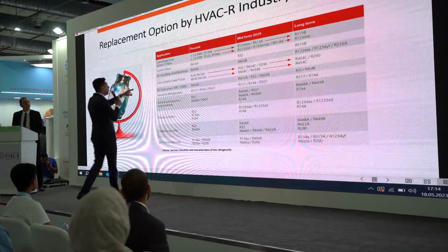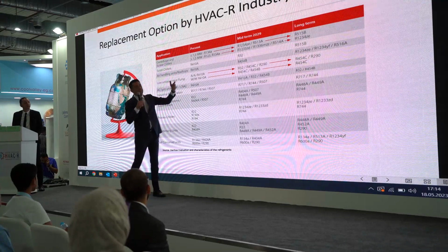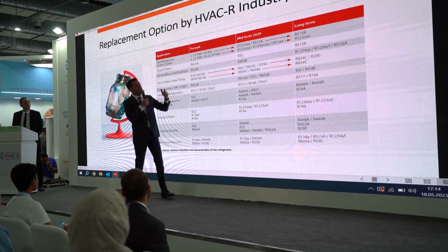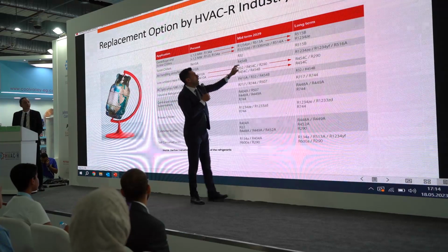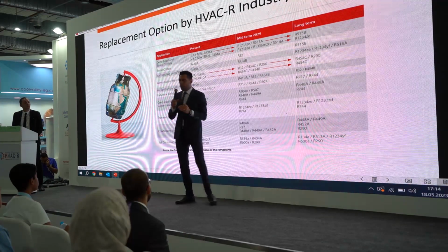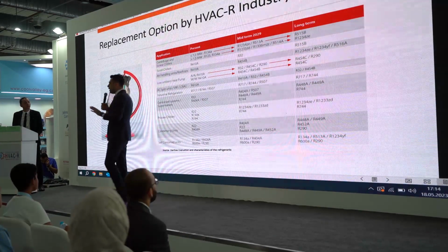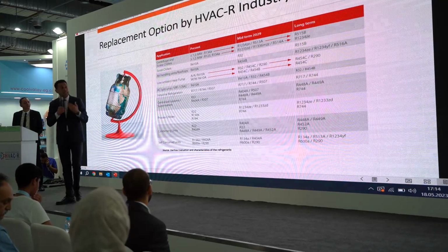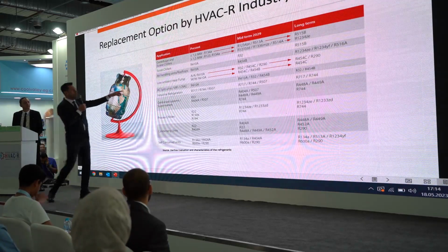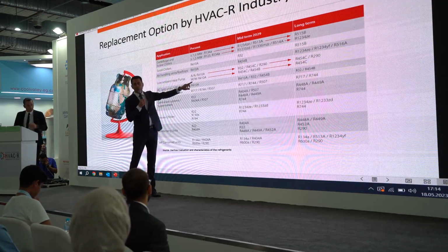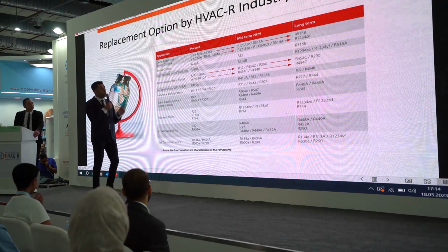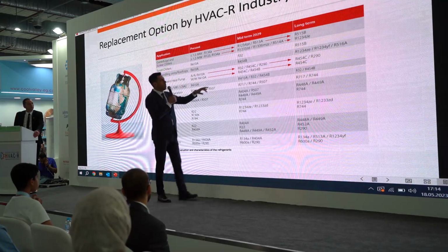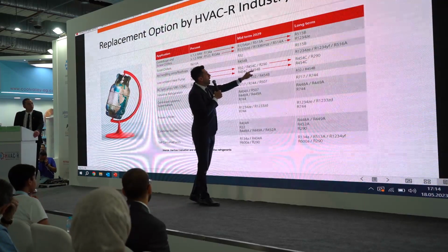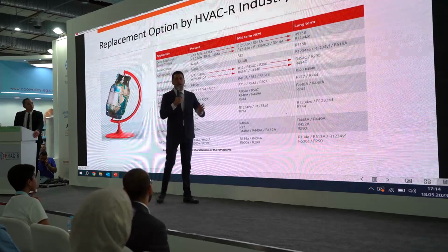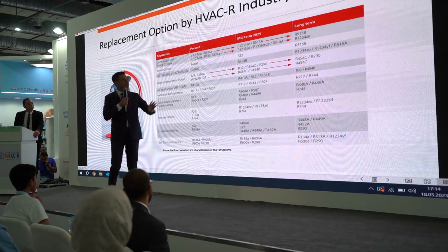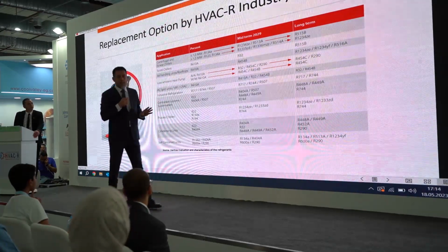If we come to scroll chillers, today, as you know, it is 410. Most probably it's going to be replaced by 32 and 454B, depending on the capacity. These are just like planning. For low ambient heat pumps, for example, today air-to-air or water-to-water is 410, but it's going to be replaced - it's already started to be replaced by 32, and over time it's going to be 454B or R290. And of course long term, different.